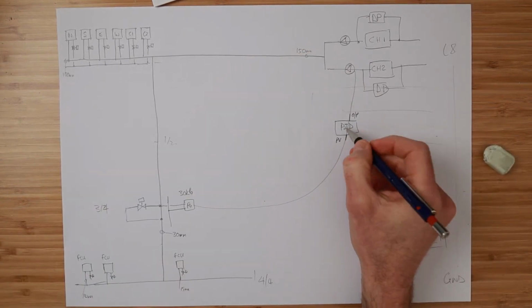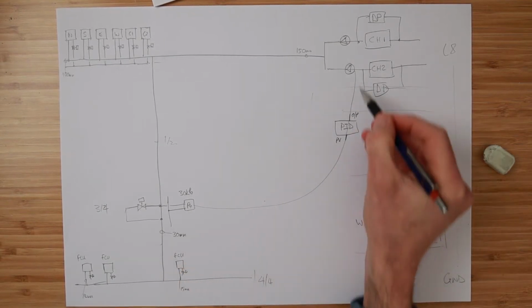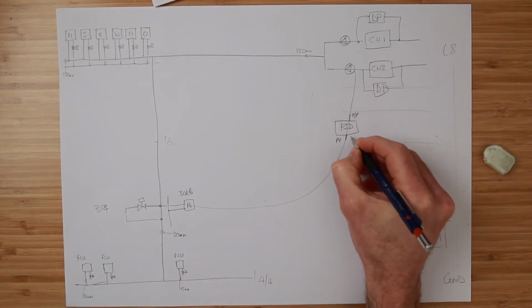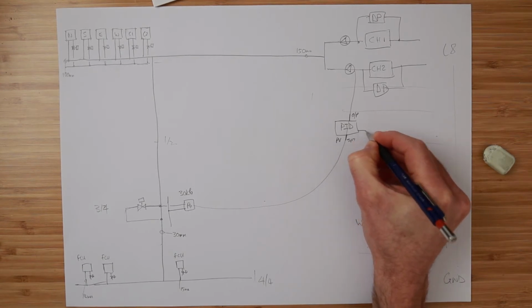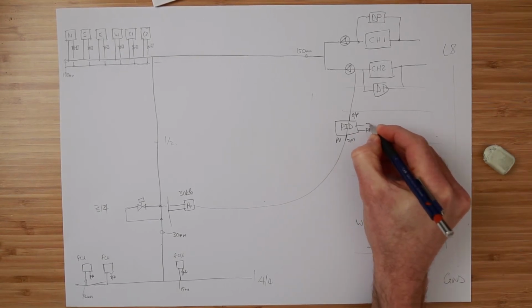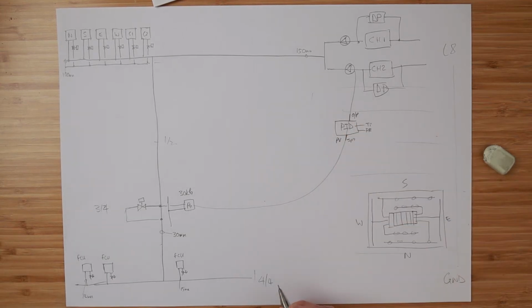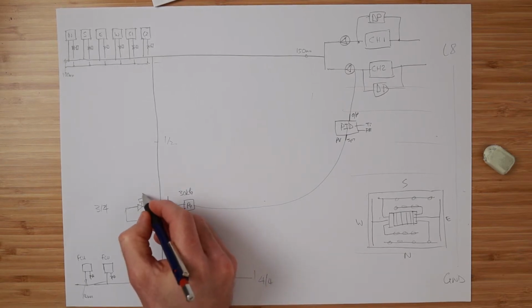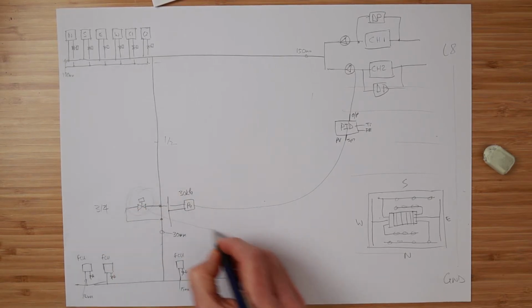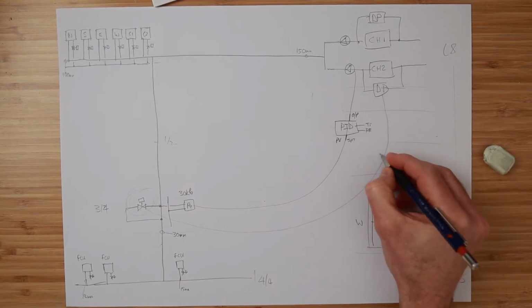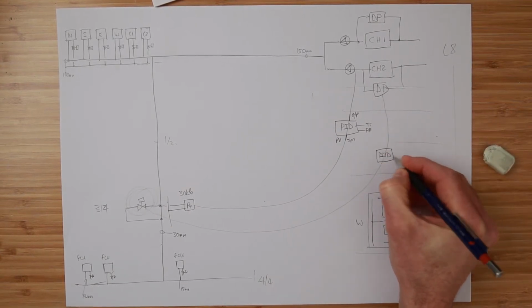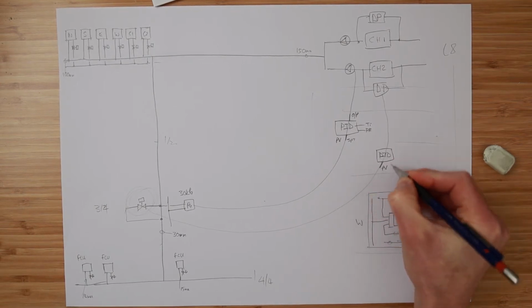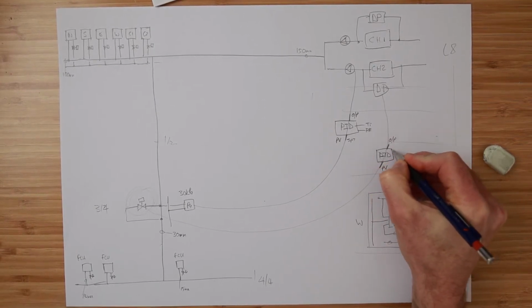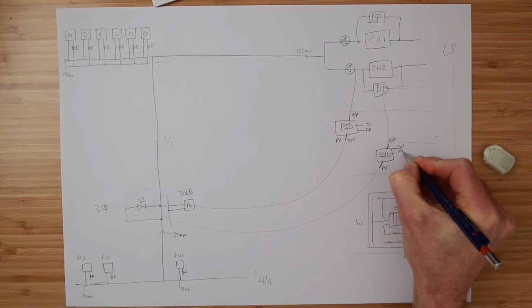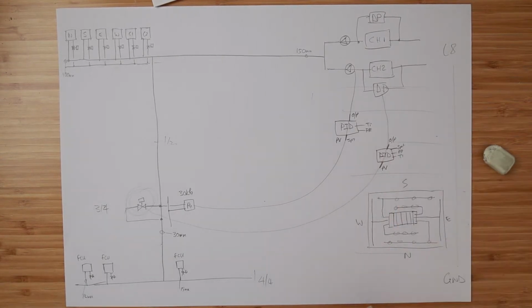So we had a PID loop, system pressure, controlling the speed of the pump. We've got a set point, we've got a proportional band, integral time, and so on, it's a PID loop, measuring the pressure, controlling the speed of the pump, and then the bypass valve. The bypass valve controls the minimum flow through the chiller. PID loop, process variable, output, set point, proportional band, integral time, etc.